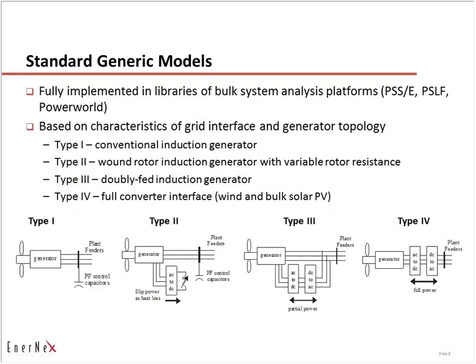Because of the range of energy conversion technologies employed, it wasn't possible to boil this down like we have for conventional generators. We ended up with essentially four types of generator topologies for wind initially. Of these four, only the last two — Type III and Type IV — are relevant today, although there is a substantial fleet of Type I and Type II turbines in the ground that still need to be represented in planning cases.